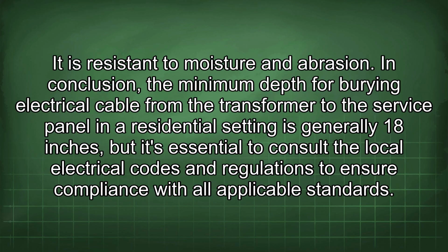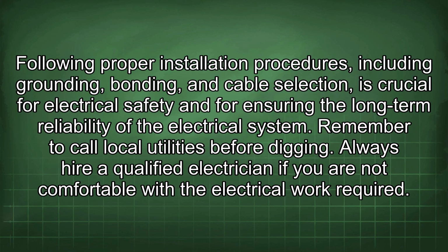In conclusion, the minimum depth for burying electrical cable from the transformer to the service panel in a residential setting is generally 18 inches, but it's essential to consult the local electrical codes and regulations to ensure compliance with all applicable standards. Following proper installation procedures, including grounding, bonding, and cable selection, is crucial for electrical safety and for ensuring the long-term reliability of the electrical system. Remember to call local utilities before digging. Always hire a qualified electrician if you are not comfortable with the electrical work required.